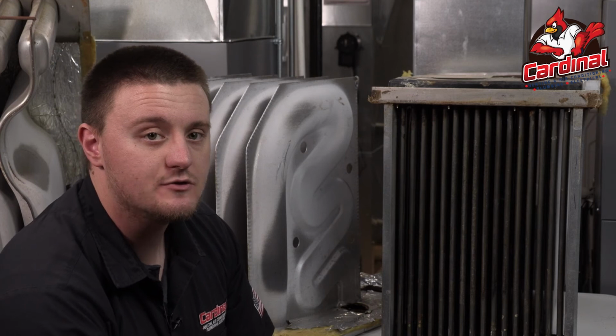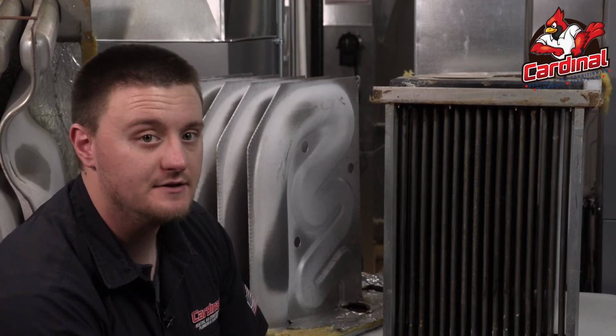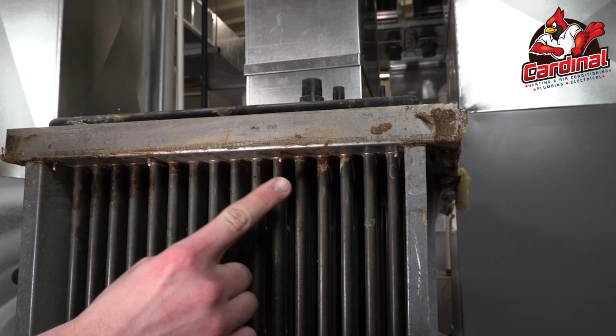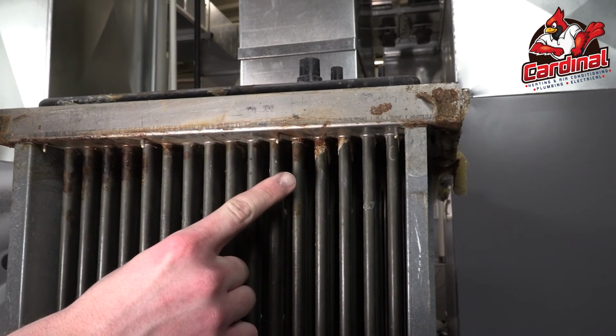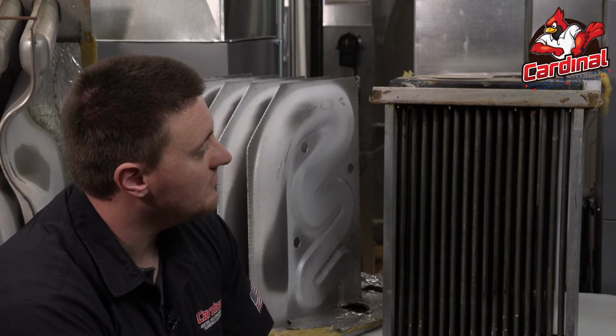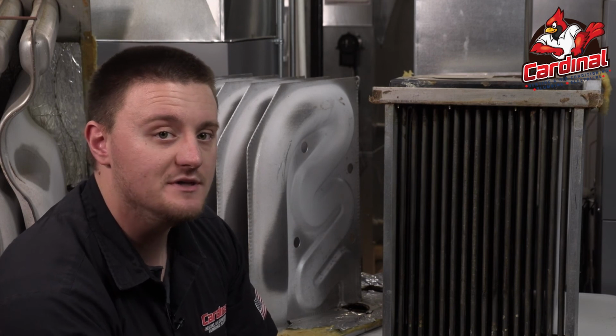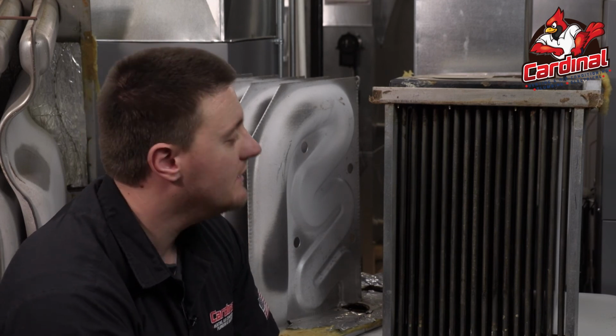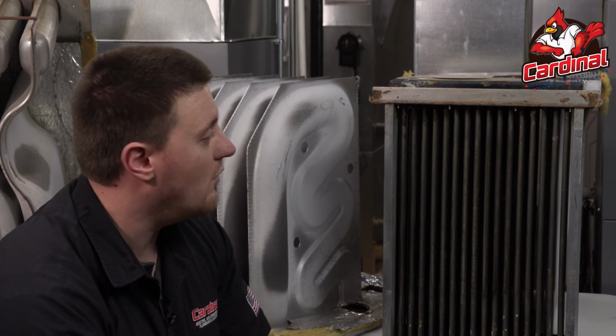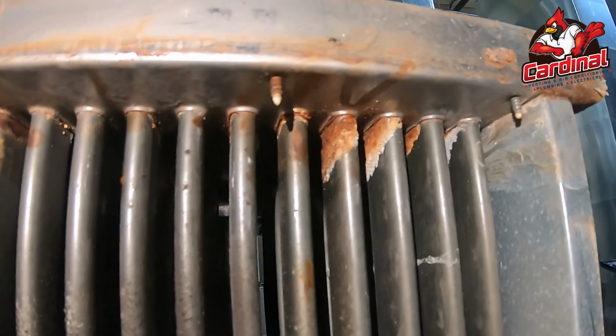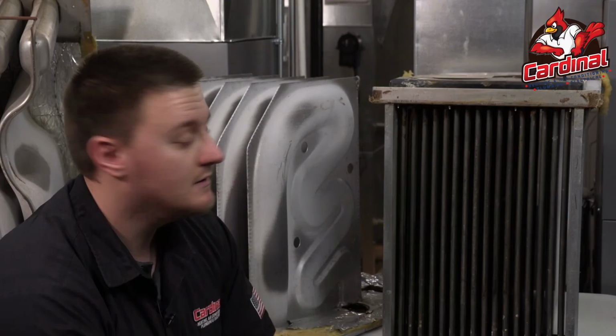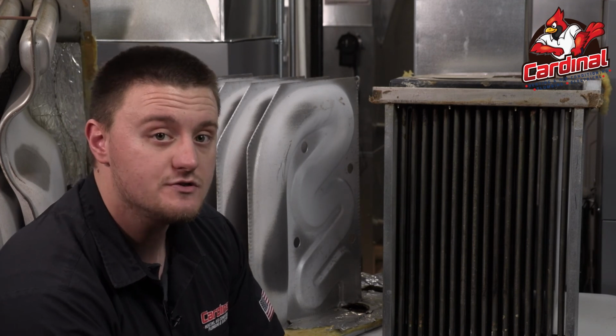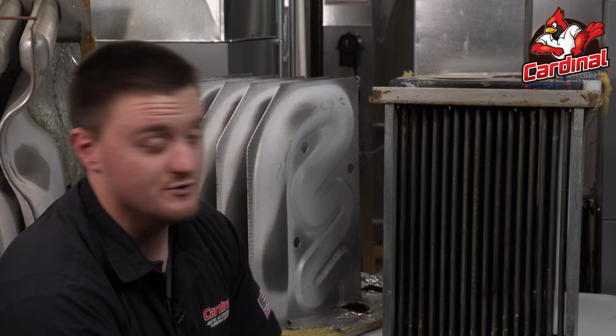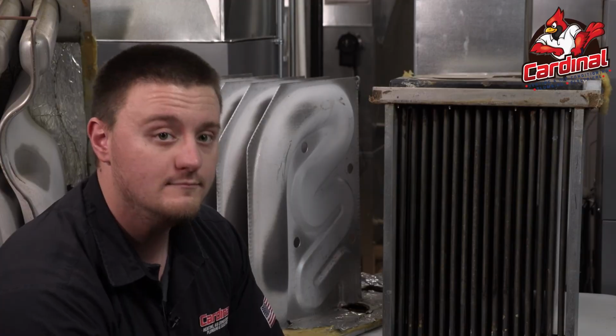This one here is going to be an example of a failed secondary heat exchanger. Right up here, you can see some corrosion that's built up at the base. What that is from is excessive moisture building up inside the secondary heat exchanger. And we call this a breach because that water actually busted through the metal in the heat exchanger. And this is still considered a failure, so we need to shut it down because this will also push carbon monoxide into your home. It is critical that your heat exchanger is in good working order to keep you and your family safe.